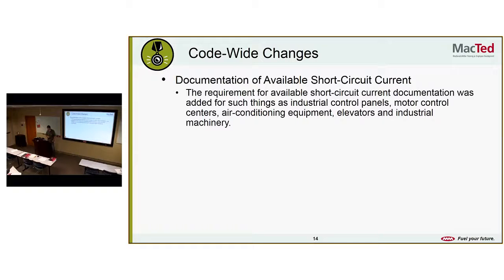Requirement for available short circuit documentation was added. You've probably seen those on control panels, industrial motor panels, switchboards, short circuit ratings now along with arc flash requirements for what type category of gear. They're branching more and more. Arc flash, of course, as we all know, is a big thing, and so is short circuit ratings. So now they're making that more and more available on nameplates.